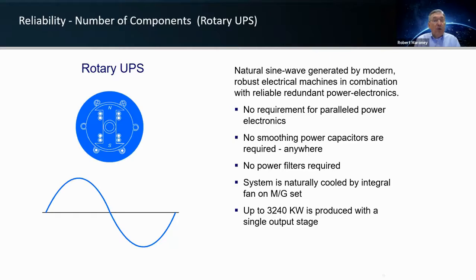You only have one fan in the entire UPS system, and it's a mechanical fan. You'll see it in a minute where it's connected to the motor generator. You can also go to very, very large capacities in a single module system. So thus you have a lot more real-time uptime, lower maintenance intervals, and we believe a higher, more reliable system. And we'll show you that that's true later on in the presentation.